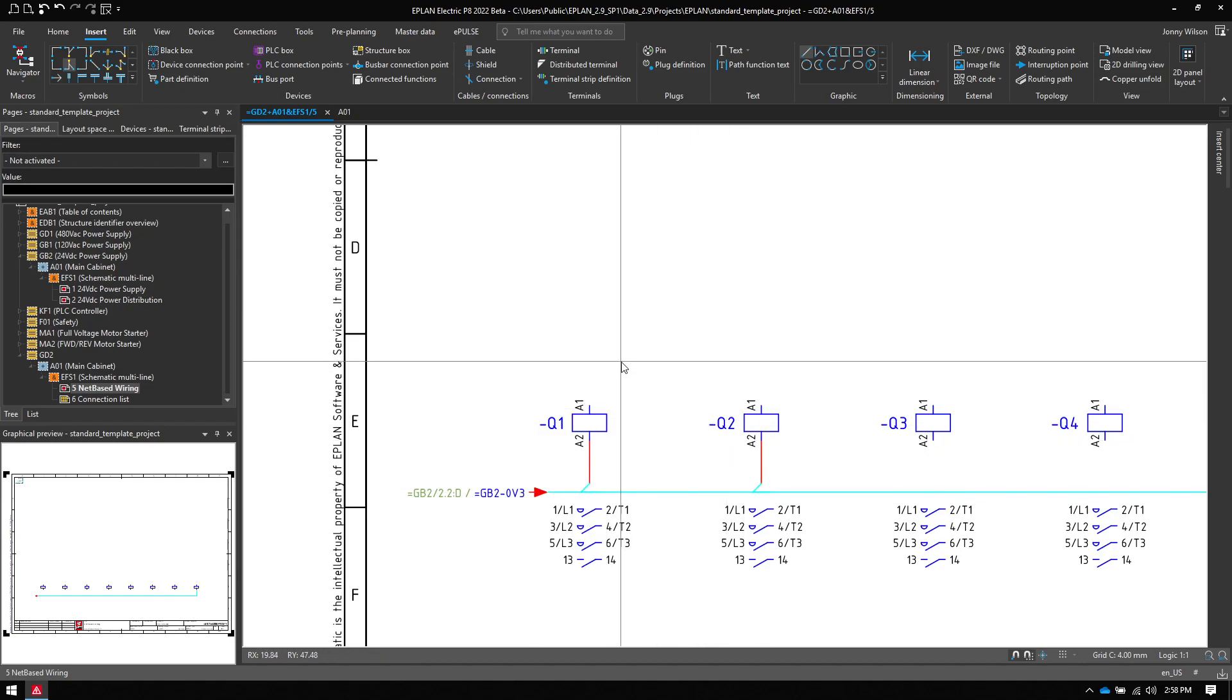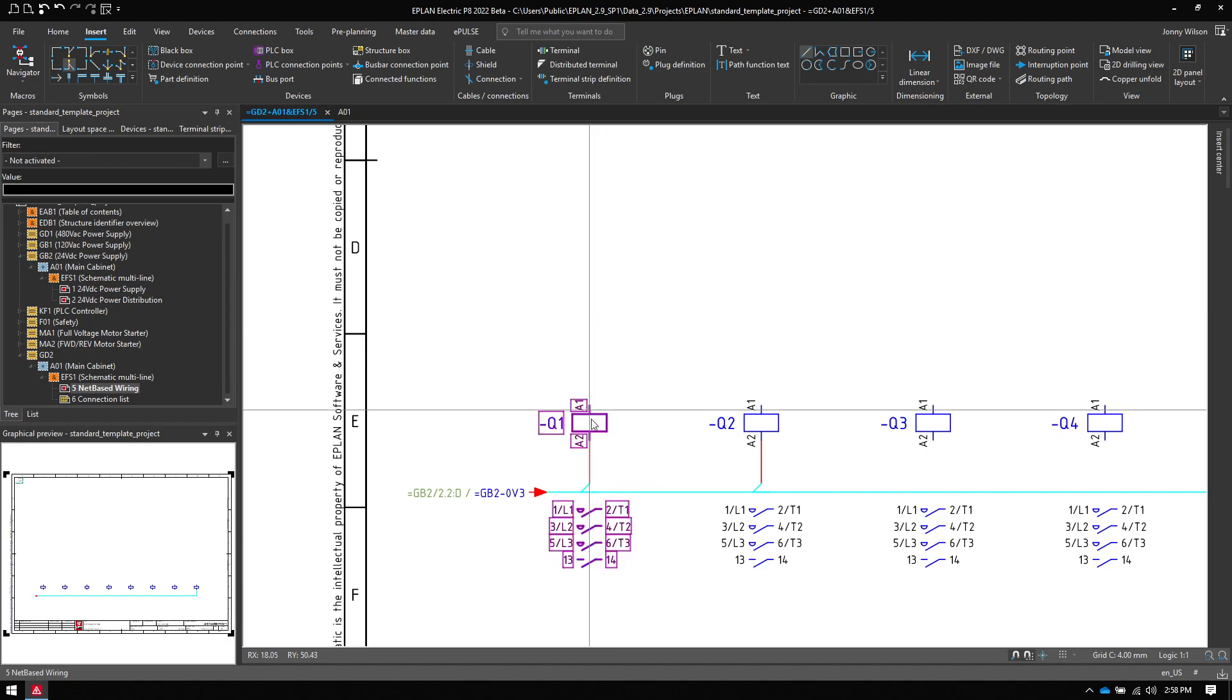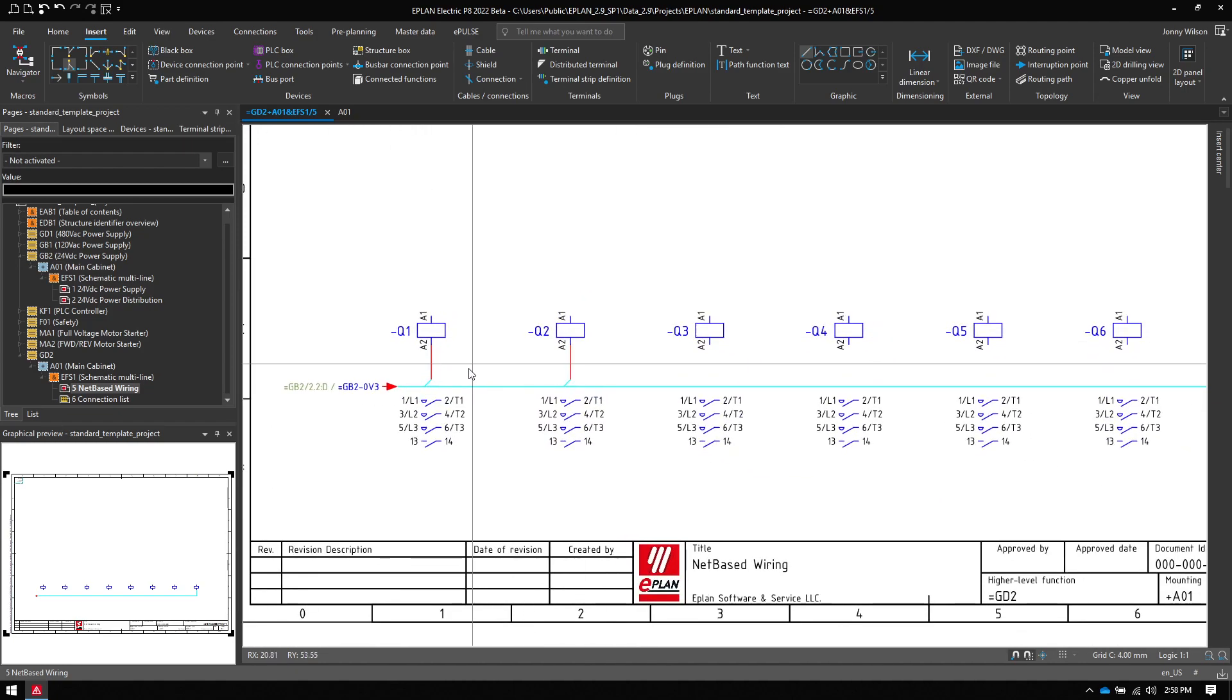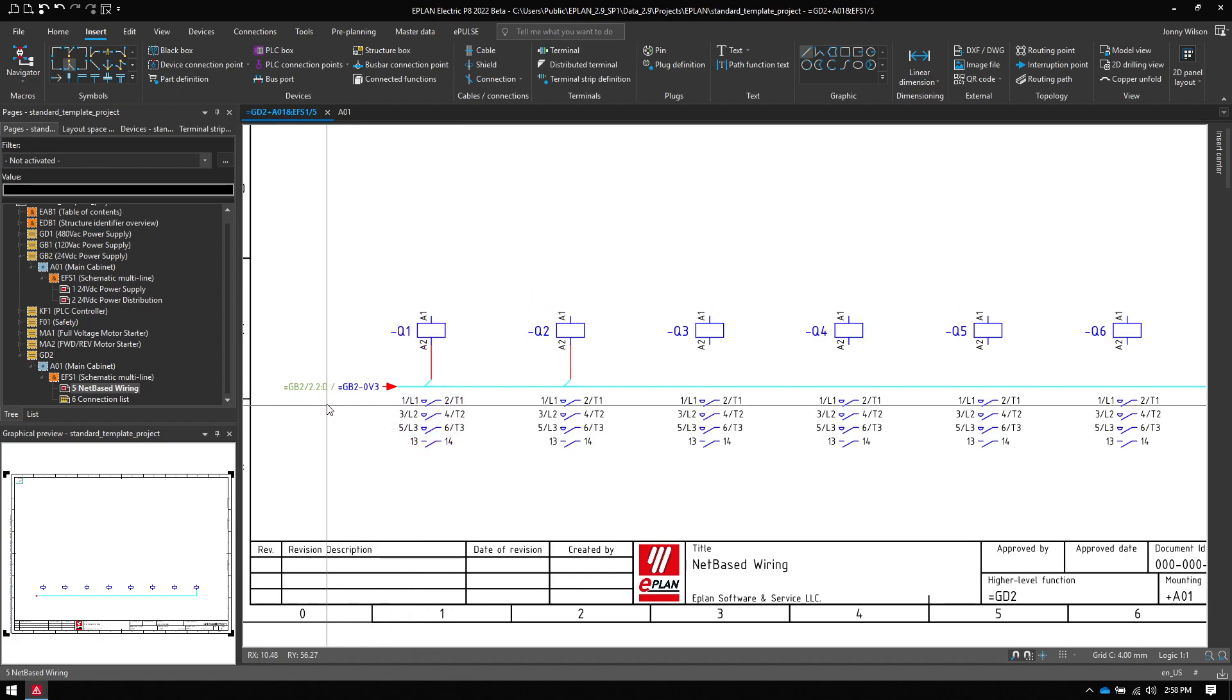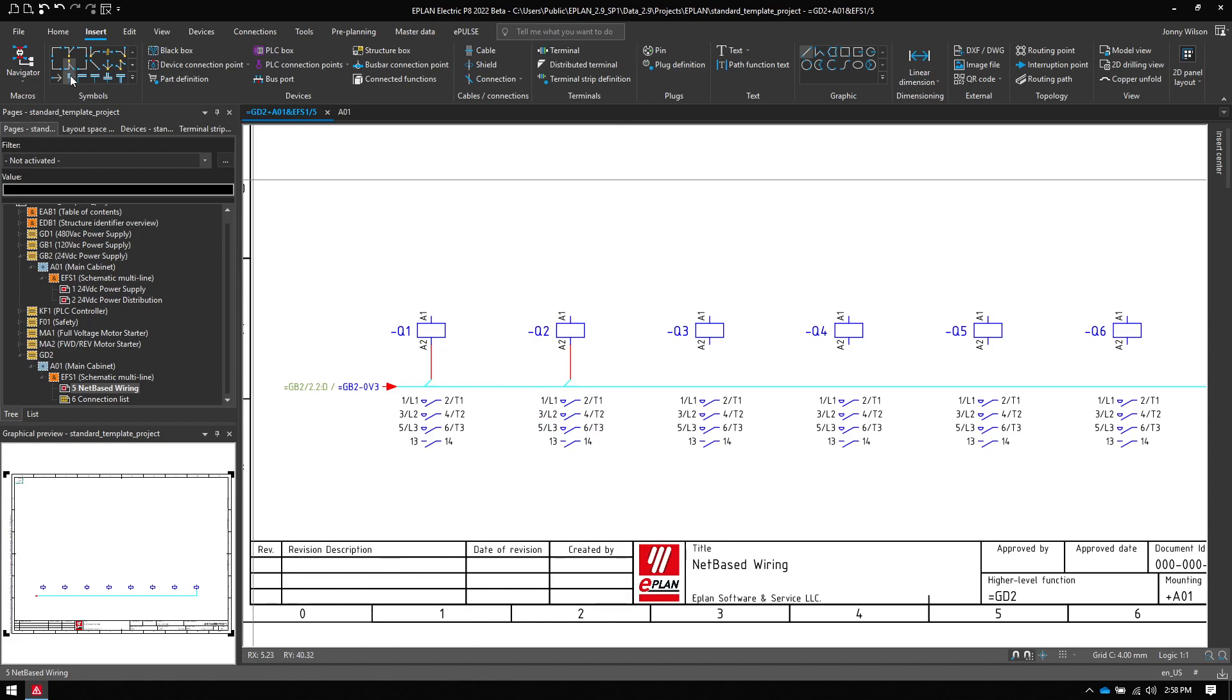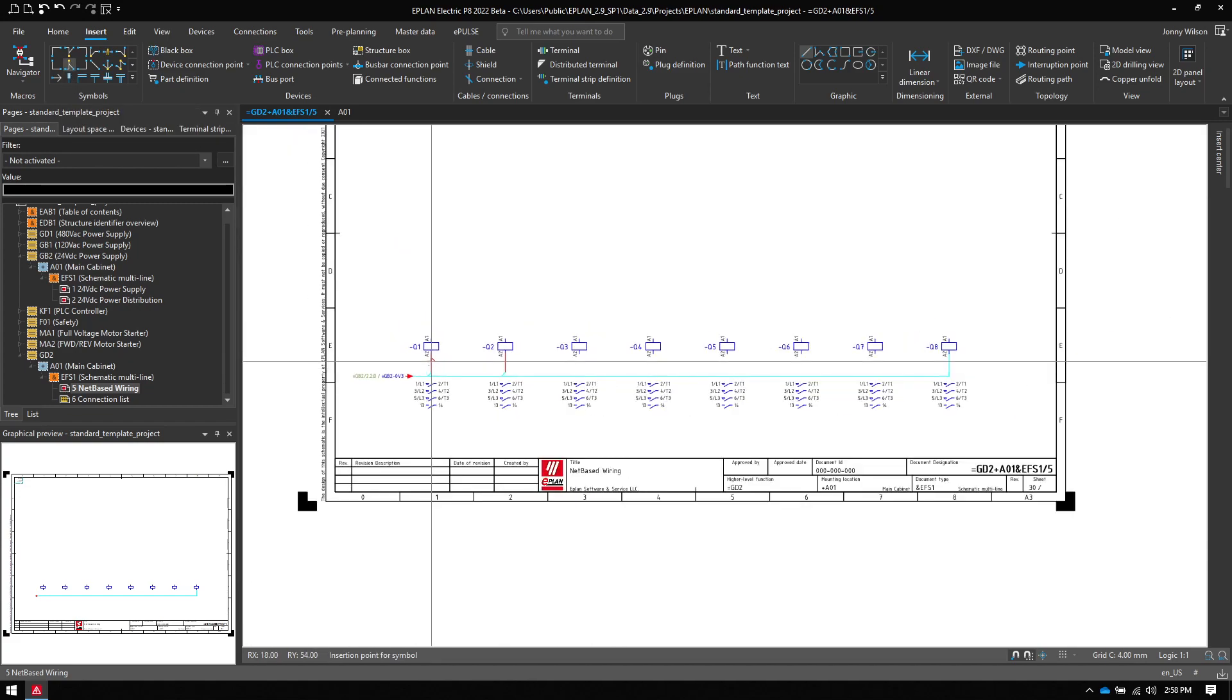this would indicate to ePlan and to the wireman that they all go back to that terminal. In reality, this T node wouldn't be correct because the terminal could only have one connection in this case. So they're all going back and that is not correct. I'm going to grab a different T node and use this one here.